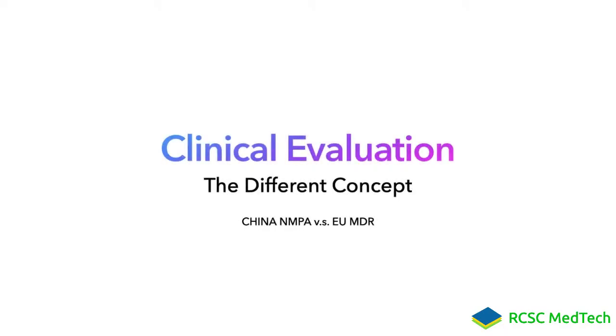Today, we will talk about the clinical evaluation report required by China and the EU in the submission. The EU MDR requirement is relatively straightforward. All medical devices, when applying CE mark, will need to submit the clinical evaluation files. While NMPA categorized medical devices into different groups based on their risks, lower risk devices generally do not require clinical evaluation reports. Instead, the manufacturer only needs to compare the device under application with the equivalent devices approved in China.